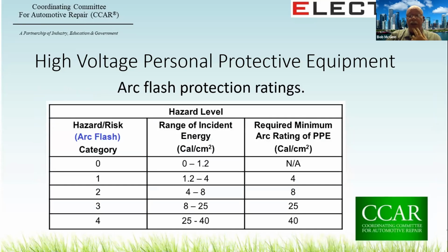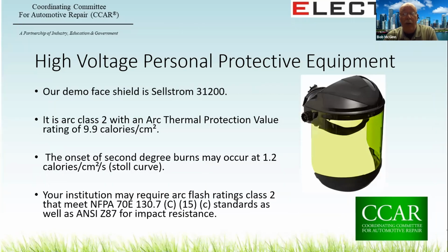This chart shows the arc flash hazard risk category as it relates to the incident heat energy, along with the minimum ATPV for that personal protective equipment. It must be noted here that resistance to heat is not the same as electrical isolation. In most cases, you're going to be looking at arc flash category 2 as the standard. You'll see why in a second. Now, I also have a demo face shield, which would have been passed around, that nobody gets to see except in this illustration.